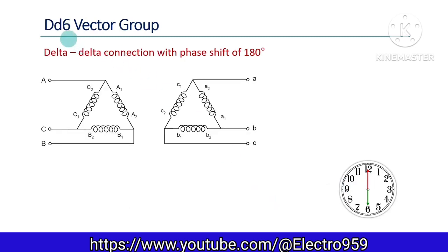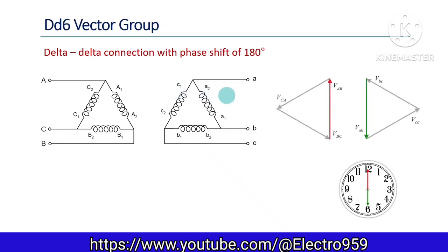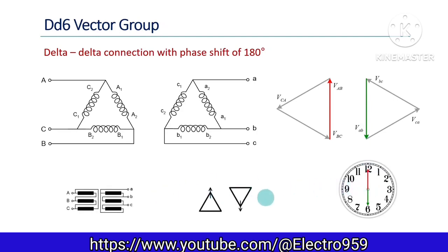Similar is the case with the DD6 vector group. Both the primary and secondary are delta connected, but the polarity of each winding is reversed on the secondary side. On the primary side it is A1, A2, and on the secondary side it is A2, A1 — and similarly in the other windings as well. This results in a 180-degree phase shift in all the voltages, again corresponding to the 6 o'clock position. The simplified connection diagram and displacement diagram are shown.